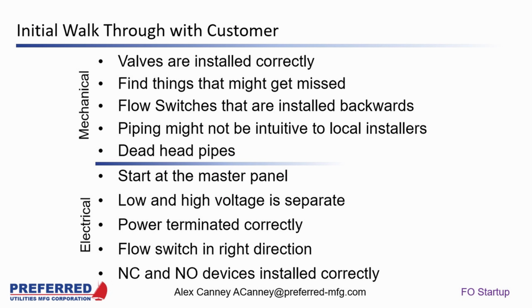That's probably the most important thing you can have done, other than the pre-startup form with the customer filling that out: to walk with the customer through the whole system, from where the storage tank is or where the pump set is, making sure any field devices are installed correctly and in the most ideal location, making sure day tanks are installed properly with the proper flow directions, like for a manifold if you're using one. All these things make it easier when you're ready to start filling a day tank, starting up a boiler loop, or even a manifold for a multiple generator system — making sure everything is piped and installed correctly makes the job that much easier.